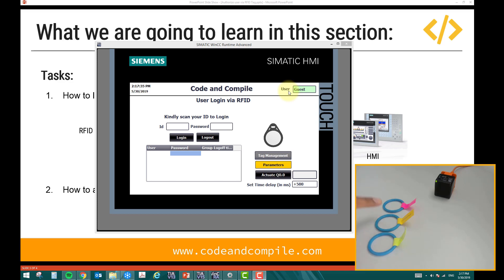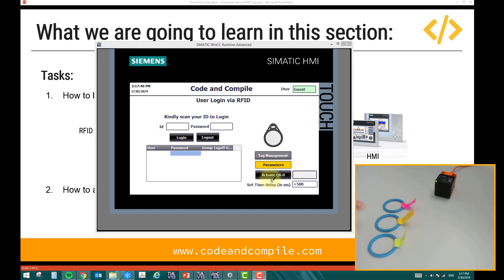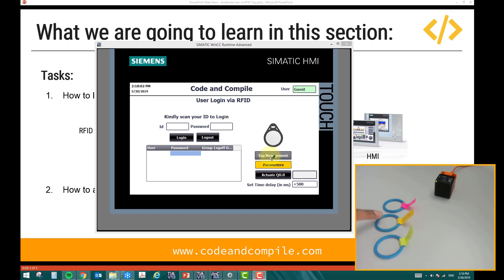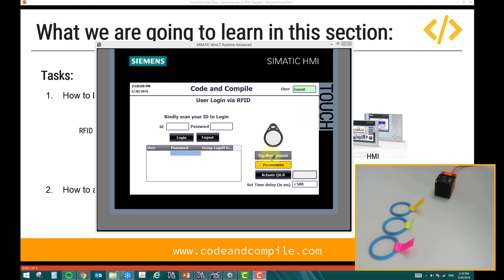On the table we have three tags: service, supervisor, and operator — the three users in this application. Each user has certain authorization. For example, the operator tag can only actuate the output. The service tag can actuate the output and also access parameters, which the operator cannot. Service cannot access tag management. Only the supervisor can do that — supervisor is the top priority and can do anything. So in order: supervisor, then service, then operator.